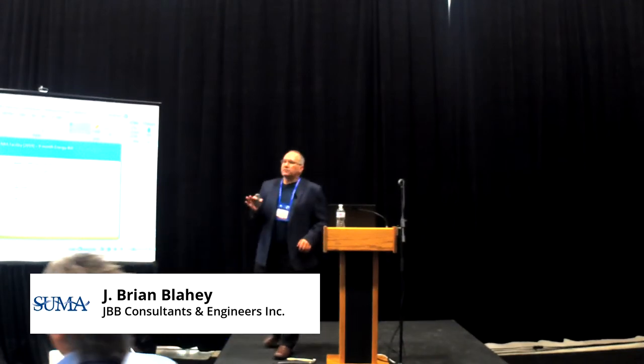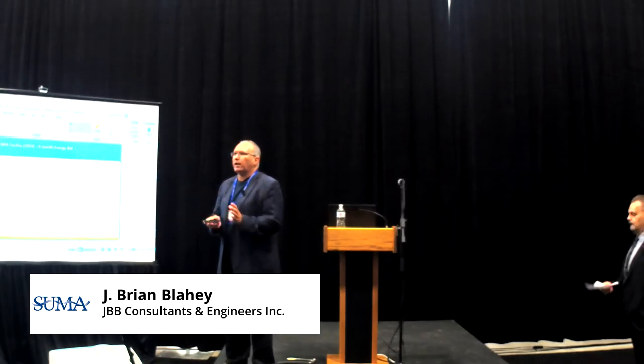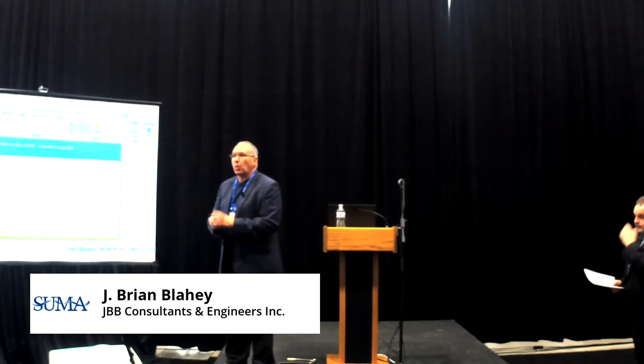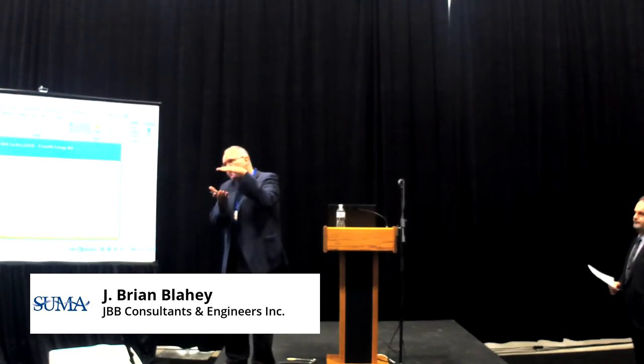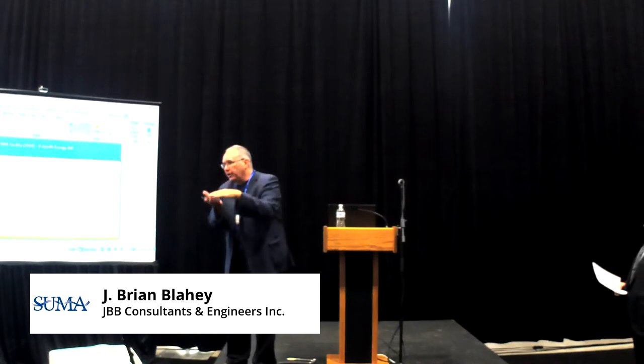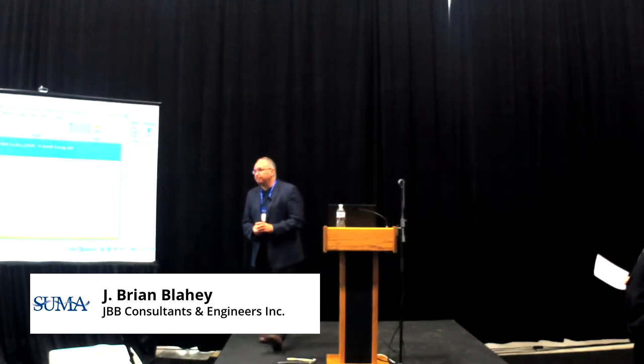One of the advantages of CO2 is that it gets very, very efficient in cold weather, so it's very well matched to our climate. That's why it's being praised so highly as an alternative to the existing systems. Your existing system has to run at a certain pressure to make sure it stays running. It's not able to float your head pressure. With CO2, you're able to float it. As the temperature drops outside, the efficiency gets even better. You run even fewer compressors, which is where a lot of the savings come from.